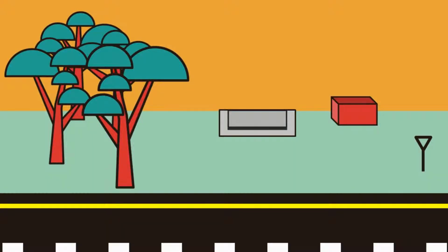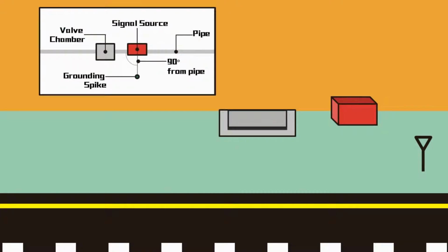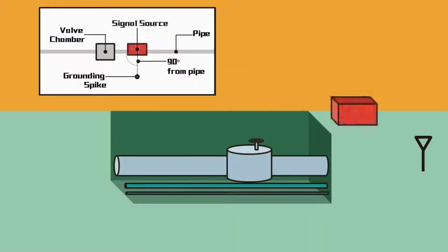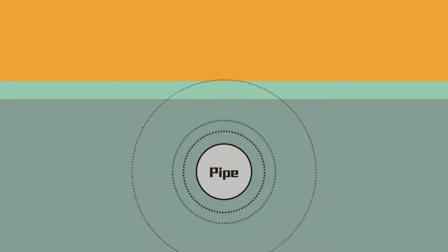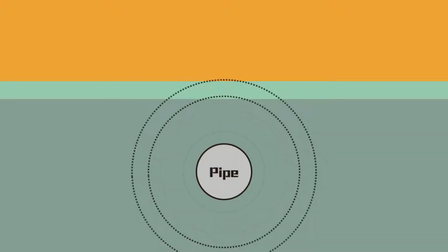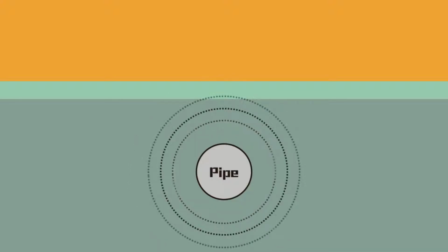The principle is that on a site, and after reading the not-so-accurate record drawings of the UU, we can open a valve chamber which connects the pipes. Then on one end, we inject an alternating current into the pipe, and on the other end, ground the circuit somewhere away from the chamber. Now a circuit is made, and the alternating current flows through the pipe. Magnetic field is then generated radially and in all directions, centered on the alternating current where the pipe is.